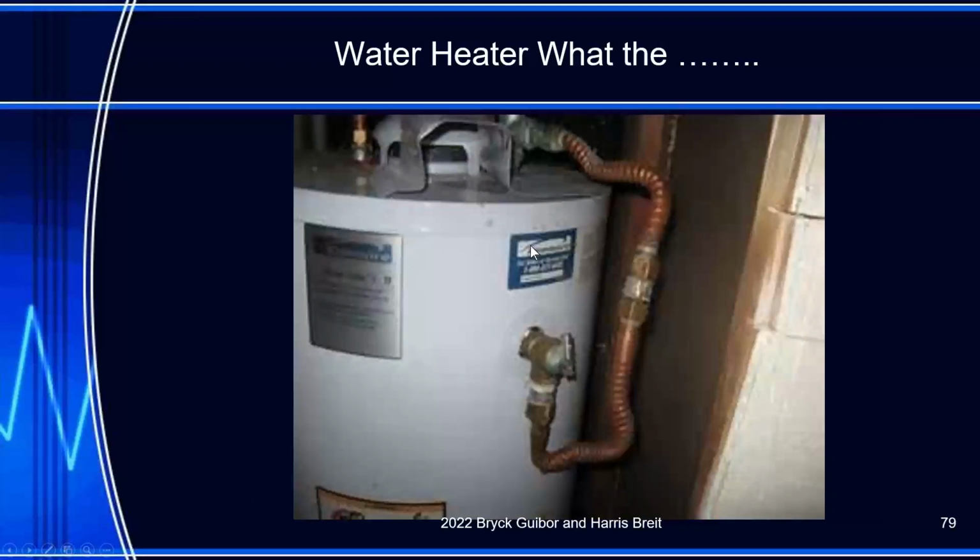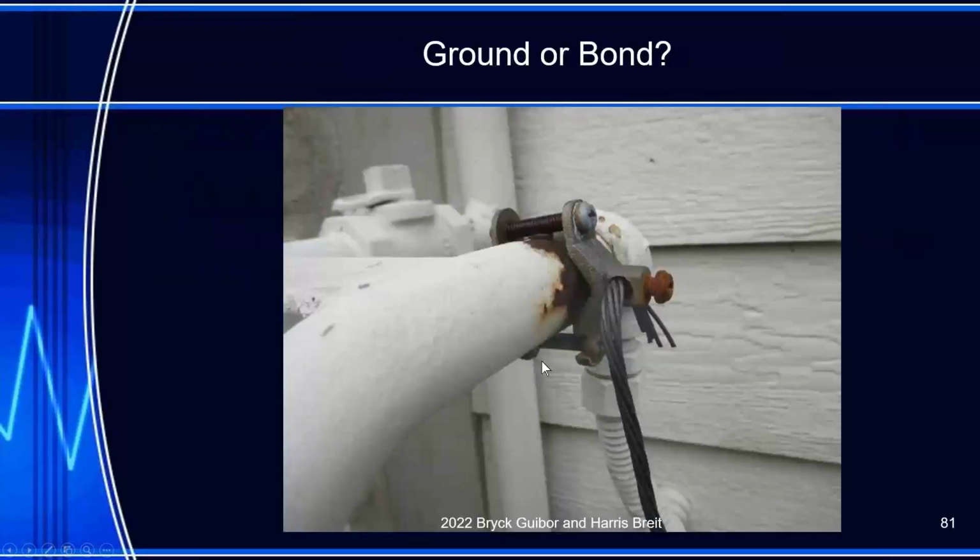Okay, again, this one's out of focus. Somebody sent it to me. It's trapped. It comes down and back up. And some of you will write this up anyway. The inside diameter of this pipe is only 5/8. And I have to have what diameter of pipe coming off the T&P valve? 3/4 inch. They make a 1-inch flex pipe that'll work for that, and you can use it.